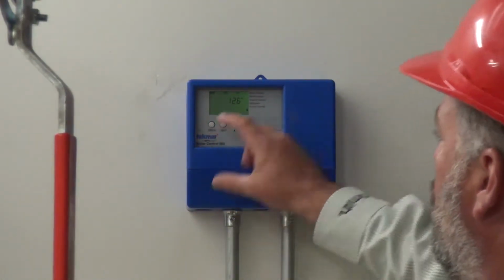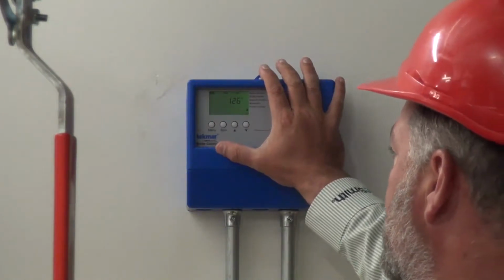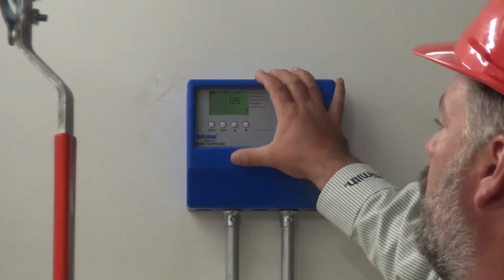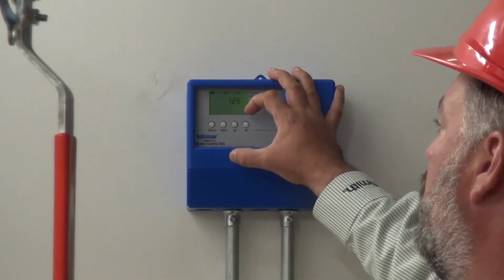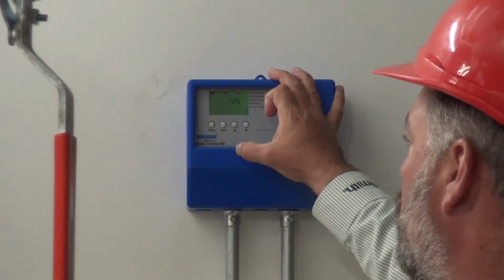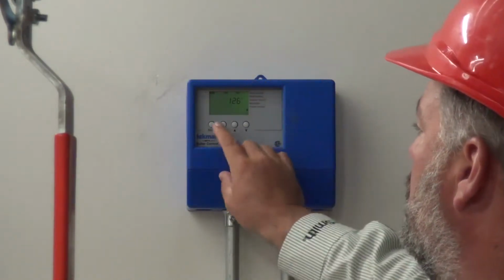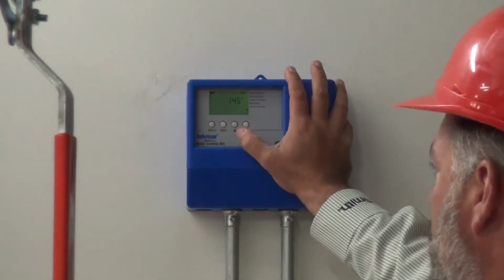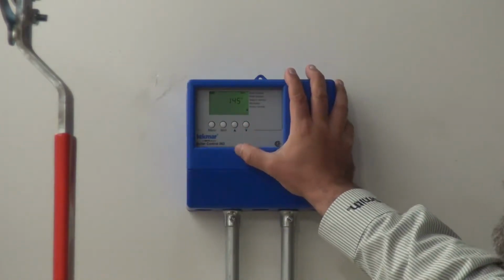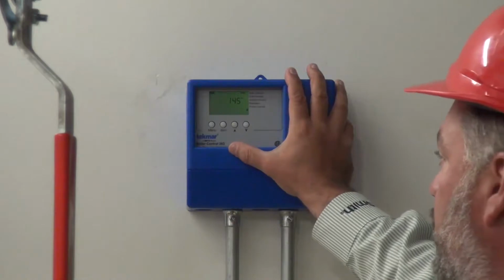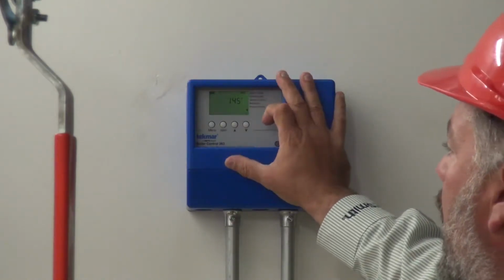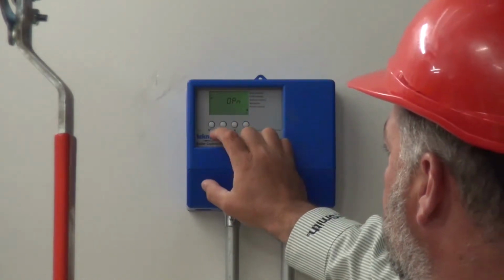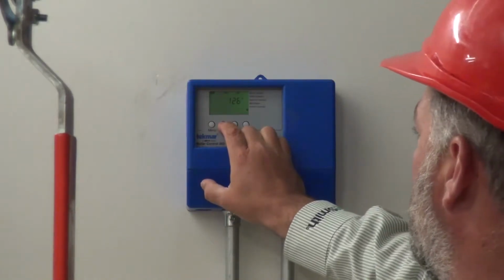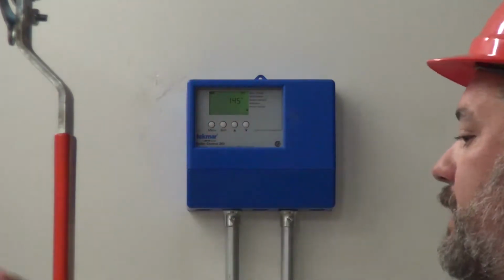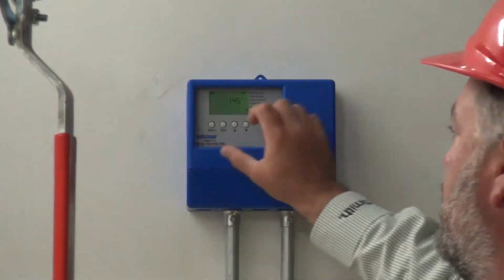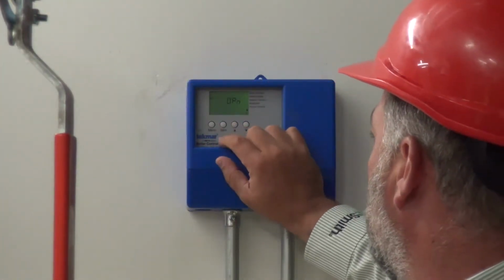As we toggle through, we're going to see boiler supply temperature. This is reading the inlet supply to the boilers, and it's showing 126 degrees right now coming through. We hit item again, it's going to show the demand. We've got that set to 145 degrees, so domestic hot water demand is at 145. That's basically what we showcase on the view screen: the inlet coming into the boiler, and the tank demand temperature set on here.